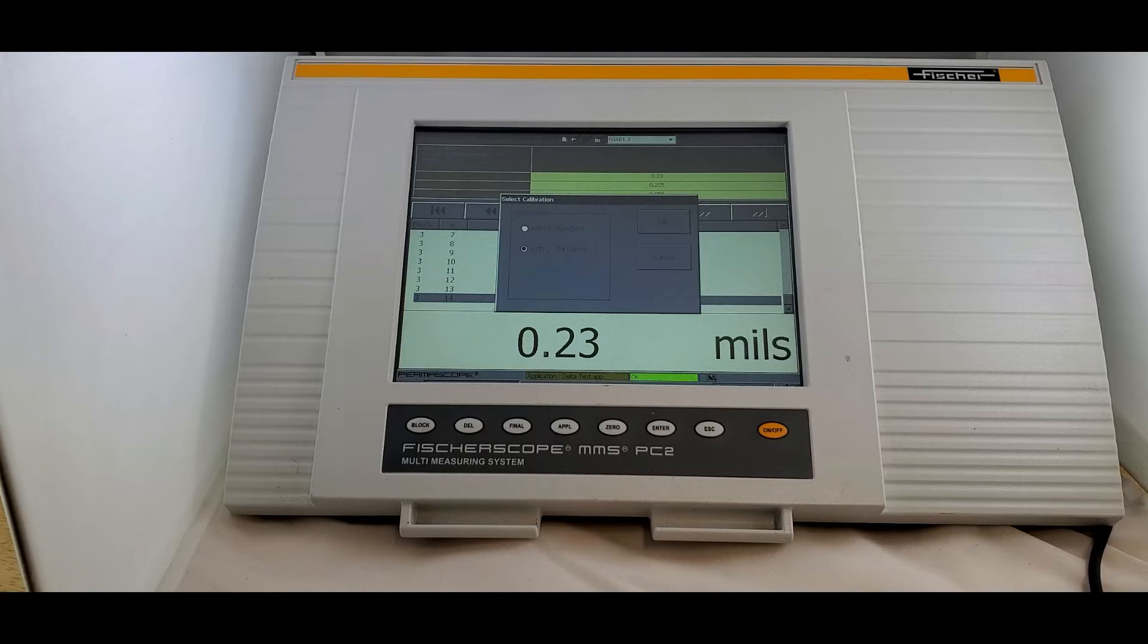Select calibration. How do we want to calibrate? Do we want to use one or two standards? If you have the option of doing two standards, do two standards.